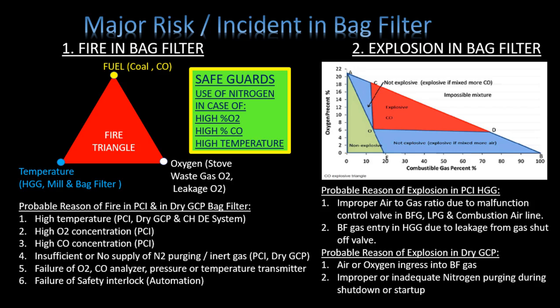Now let's discuss bag filter safety. The major risks are fire and explosion. Considering the fire triangle — fuel, oxygen, and temperature — when these three elements meet, fire is possible. In PCI, fuel available is coal and carbon monoxide gas; oxygen can be present in the stove waste gas line and from leakage in duct flange joints; temperature is available at the HGG and mill outlet. This can result in fire, causing asset damage and unplanned shutdown.